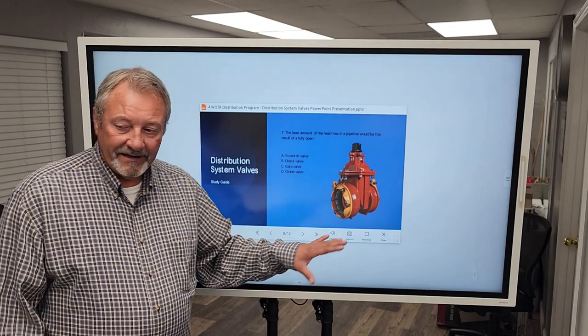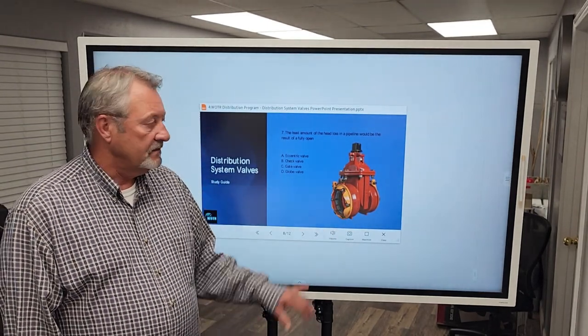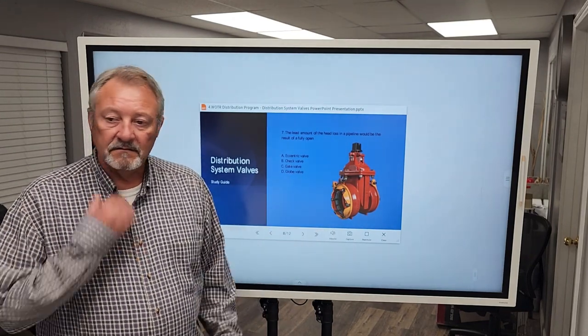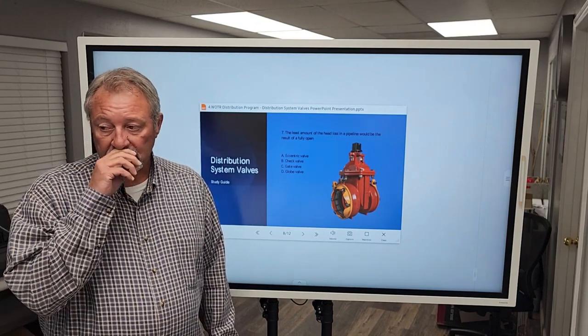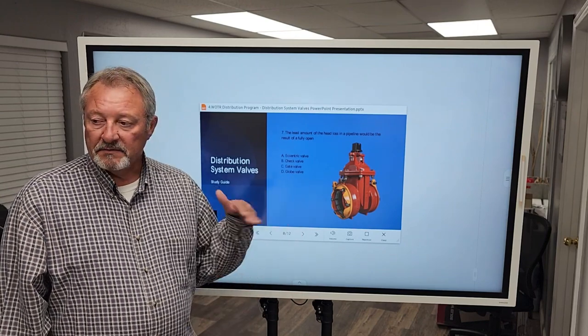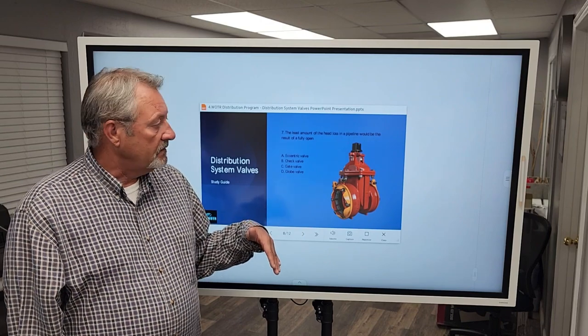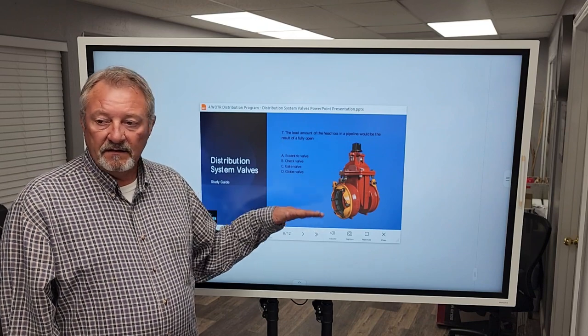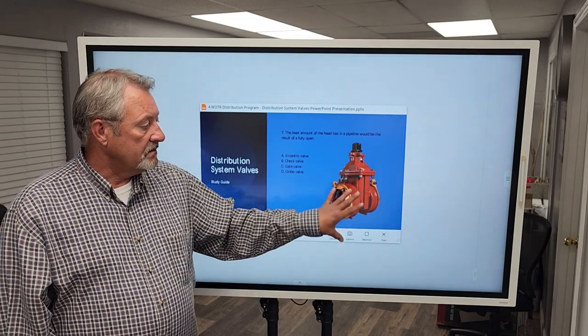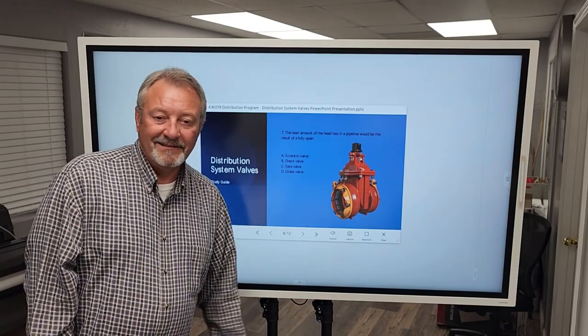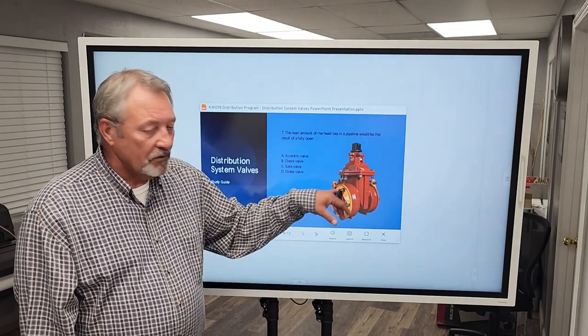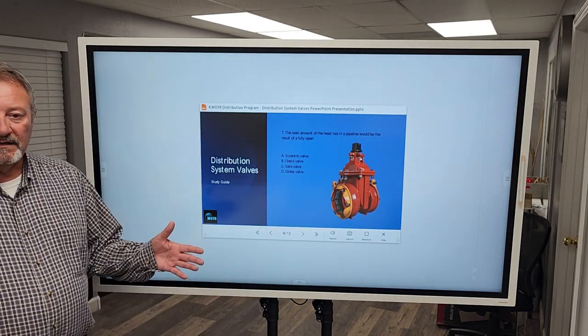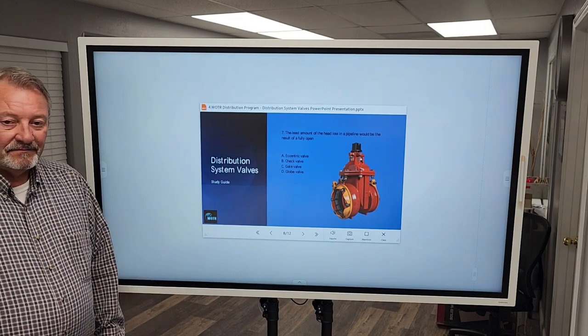So with all that said, Brian brought this up. It was a really good question. What type of, who makes this valve? It's Romac. It's an alpha. It's an alpha gate valve. They make alpha couplings. We use a lot of those. Because unfortunately in this system, it was owned by a utility before us that didn't really maintain their system, didn't build it very well. And we've had a lot of problems with pipe splitting underground because of poor backfill. That's another video for some other day. But because we experienced that on forced mains and water mains, these Romac alpha couplings, and they're not sponsoring me, we're not getting paid to promote. Thanks a lot, Brian. You're welcome. But they are really quick. It shortens that 40 minutes, 45 minutes down to five minutes, 10 minutes. So simplify it. It's an industrial hose clamp.